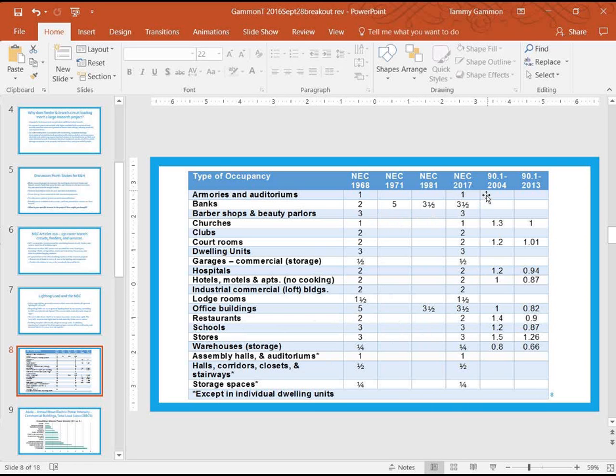If we compare that with ASHRAE 90.1 2004 and 90.1 2013, these numbers are much lower, except interestingly for warehouses, which is 3 to 2.5 times the requirement of NEC 2017. I'm interested in ASHRAE 90.1 2004 because I researched the DOE reference models for commercial buildings, and for new construction it uses the 2004 edition of 90.1. I haven't gotten a response from DOE yet on what substantiates their use of this table for current new construction, not specifically energy efficient construction, just their reference model. My guess is these 2004 numbers are probably more realistic than what the NEC has.